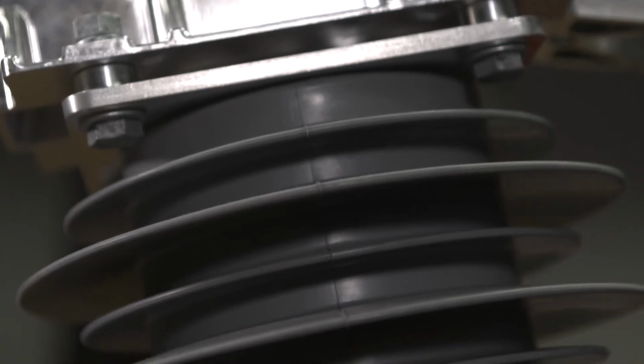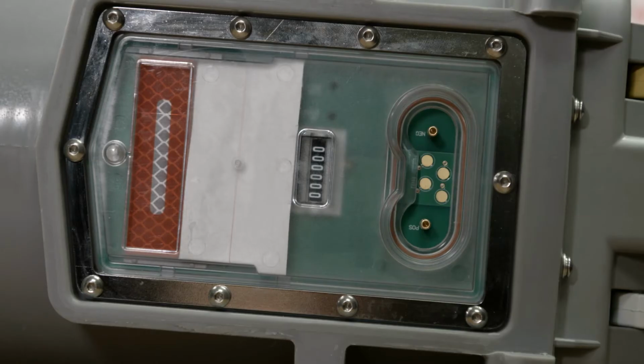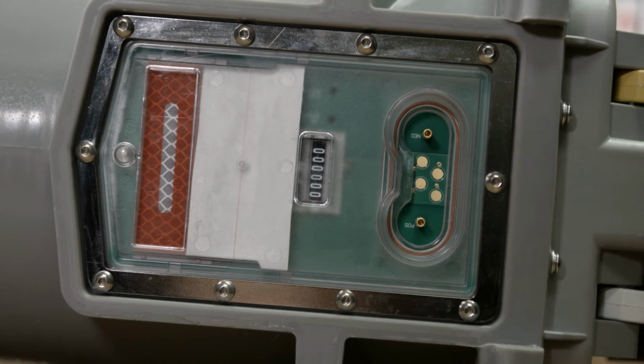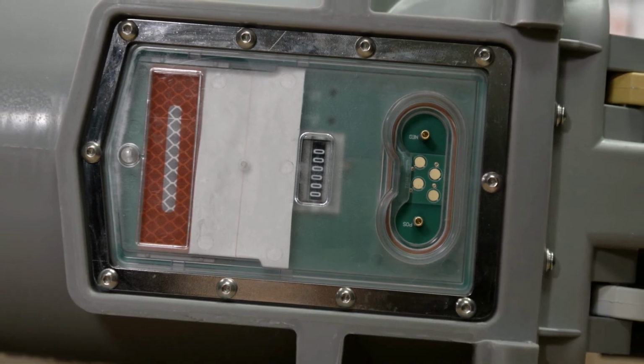Siemens Compact Modular Recloser can be supplied with its protection pre-configured so that it can be dropped in place of existing oil-filled reclosers with no need for any setup or configuration. Each of its 4 shots to lockout can be configured with any combination of curve, and each of these can be modified with either multipliers or time delays to optimize coordination. As an integrated device, the CMR's electronic controller and accurate sensing CT ensure precise protection performance.